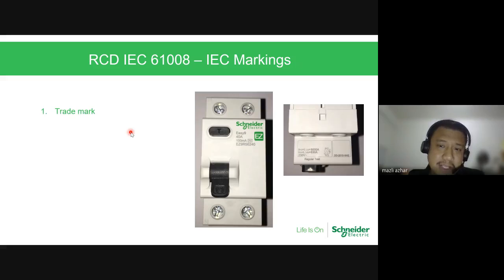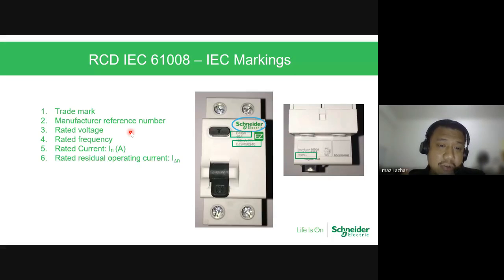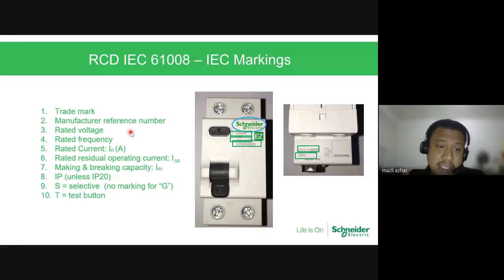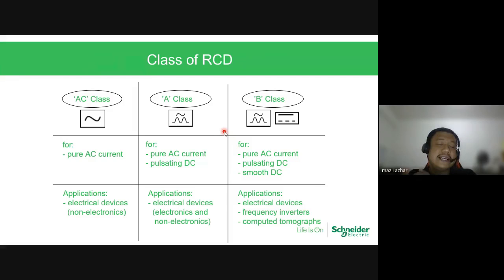So IEC marking, same as MCB, you need to have a trademark, you need to have a manufacturer reference number, rated voltage, frequency, rated current, as I mentioned, 40 amps, operational current, sensitivity, this one is 100 milliamp, making and breaking capacity, this is for the power contact, IP20, fingerproof, selective, if no marking then normal G type, test button here, this is a test button, and the wiring diagram, and also AC, A or B type. Okay. So class of RCD, AC class is for pure AC current, where it applies for electrical devices with non-electronics. So non-electronics are linear loads. All right. And then A class is for pure AC current and pulsating DC. So does anyone know what a pulsating DC is?